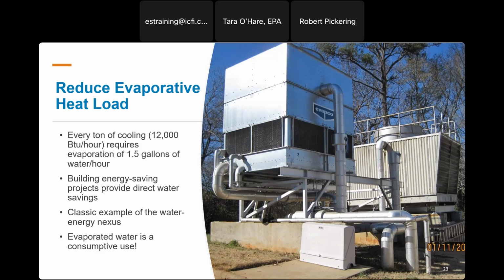That being said, anything that you can do to make your chiller plant more energy efficient will also lower your cooling load and thereby reduce the amount of water needed for evaporation. Aspects of your facility that may impact your evaporation load include building design and envelope, HVAC design and equipment selection, lighting and plug loads, occupancy, operating characteristics, and maintenance practices. For example, a lighting retrofit or system efficiency upgrade or really any other energy efficiency project can have a commensurate water savings as well from your cooling tower.